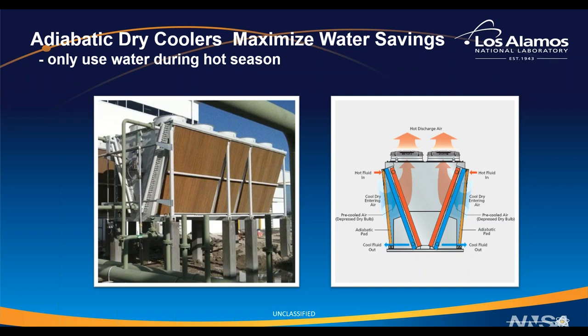The disadvantage is it's about twice as expensive as an evaporative cooling tower and takes up about six times more square footage. So as I mentioned before, for a 40 megawatt data center, it takes a football field full of adiabatic dry coolers to accomplish the water savings. Next slide.